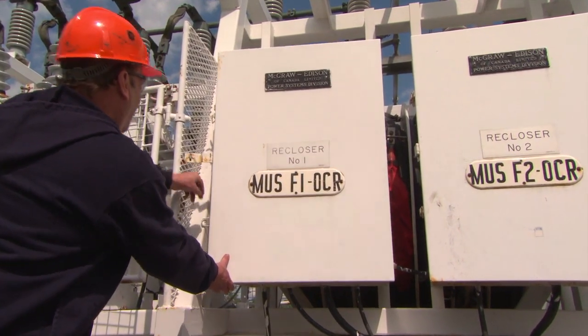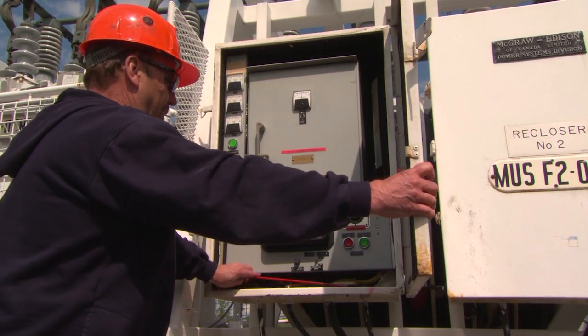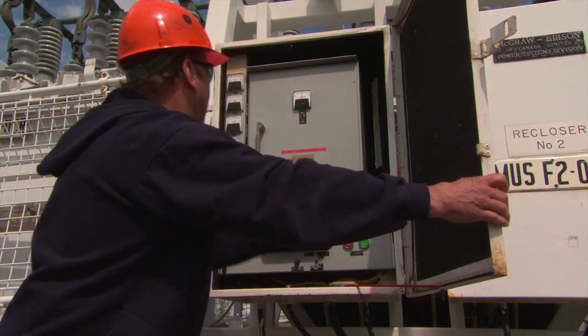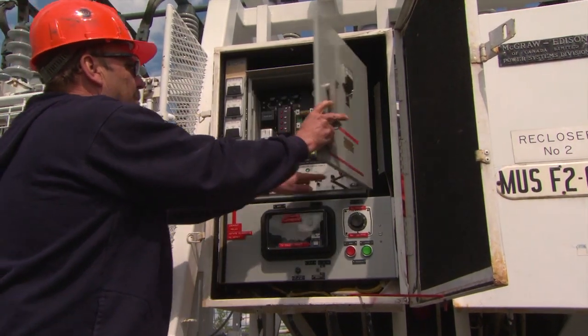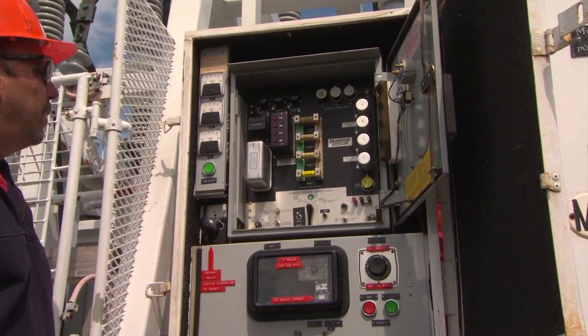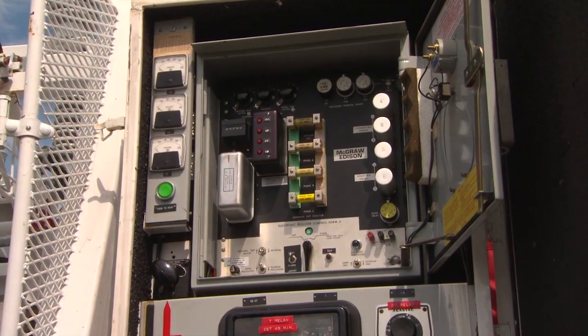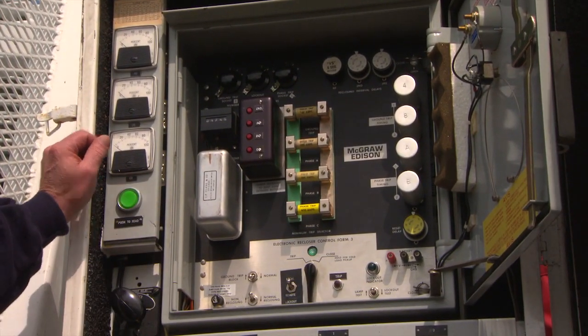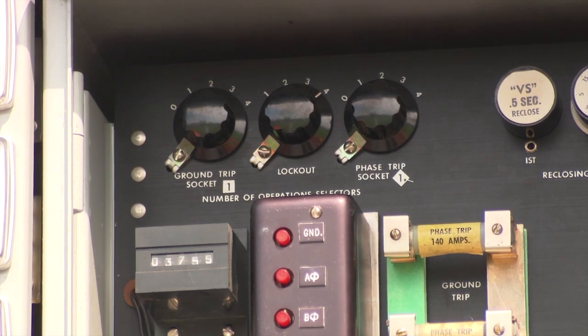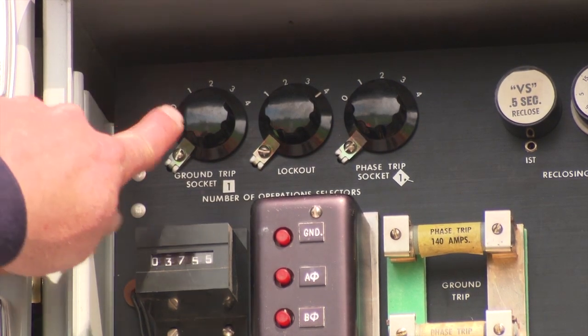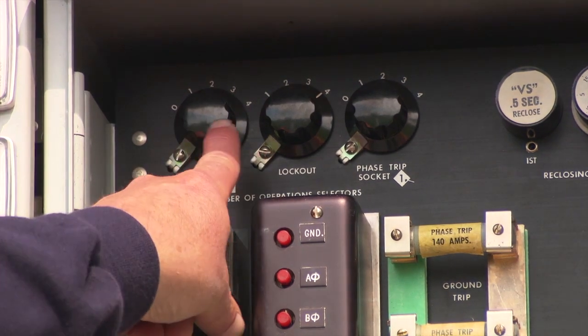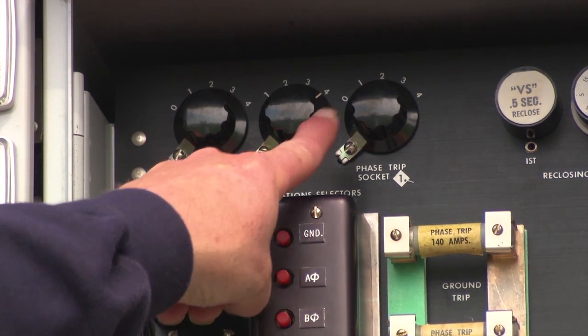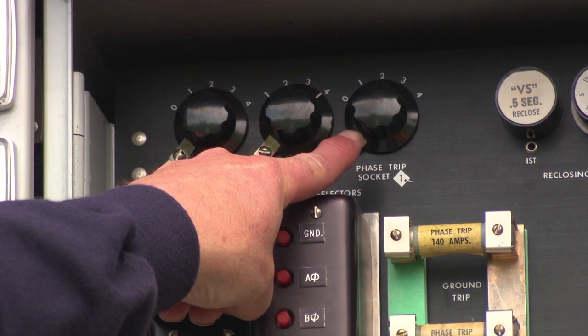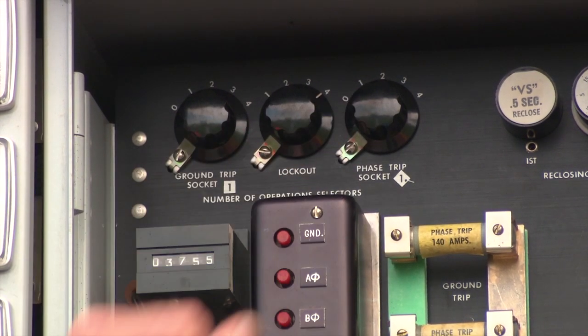Open the outer and inner doors of the F1 and F2 control cabinets and check that the various controls are set correctly. For the number of operation selectors, the ground trip socket should be set to 1. This is the number of fast ground trip operations. The lockout should be set to 4. This is the number of operations to lockout. The phase trip socket should be set to 1. This is the number of fast phase trip operations.